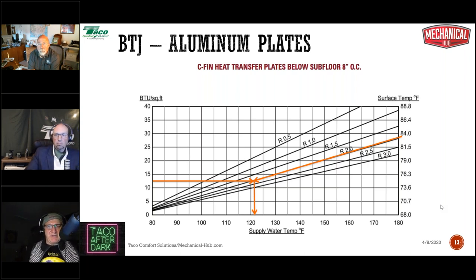A lot of people say, well, what about the flywheel effect? What about that heat? There's still heat in that system and it's giving off energy and so on. I say, yeah, it is. But even a low mass radiant system is a high mass heating system, right? A low mass system, between the floor joists with aluminum plates, is a lower mass radiant system compared to concrete, but it's still a high mass system. That mass has the ability to absorb a boatload of BTUs, a boatload of energy, without raising its surface temperature even 1 degree. A concrete slab can absorb up to like 10 to 12,000 BTUs, maybe even more, without raising its surface temperature.